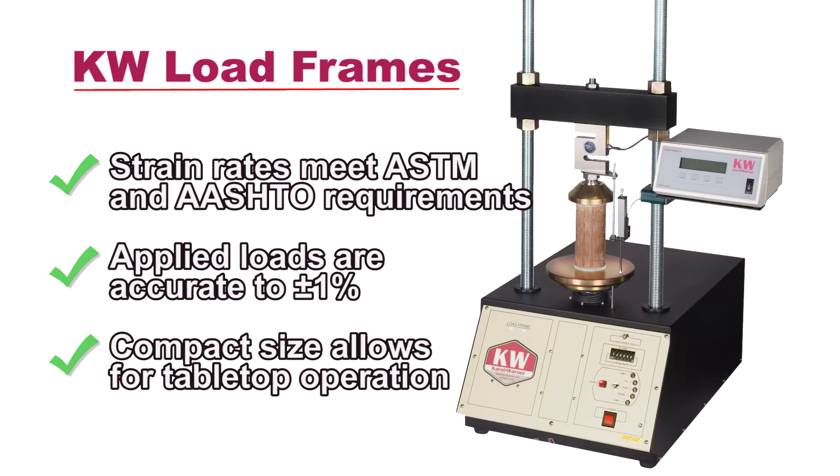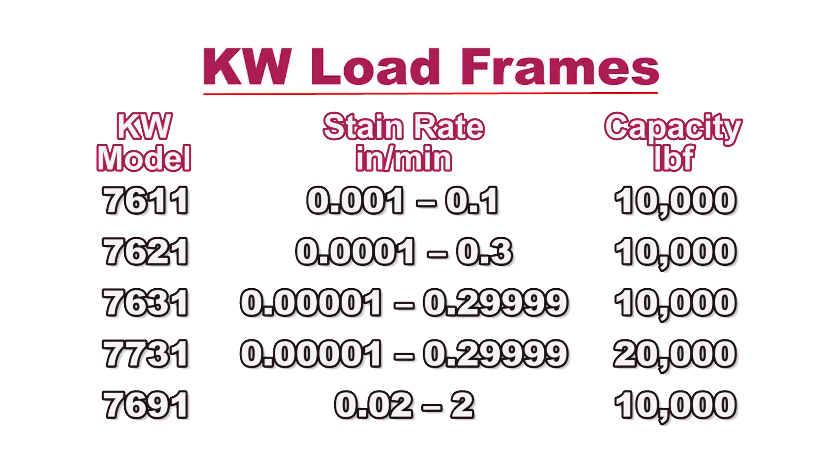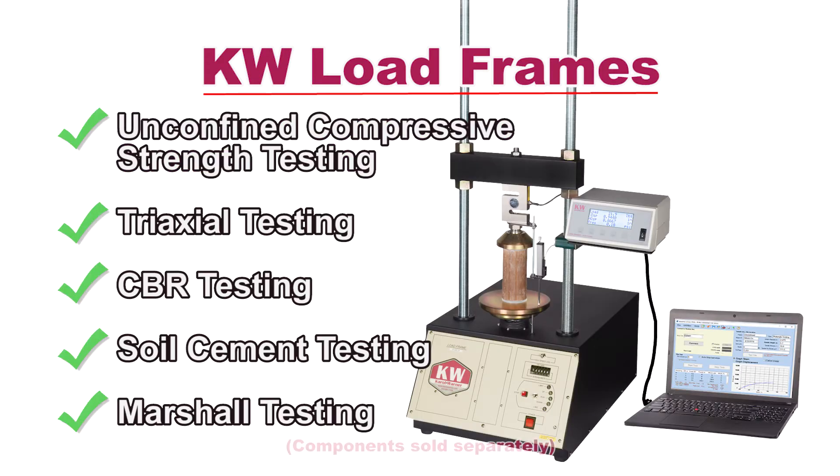Karol-Warner load frames are well suited to the strain rate and loading requirements of UCS testing. The strain rate is accurate to 1% of setpoint, and these versatile units have adjustable frame openings to accommodate many different types of testing fixtures.